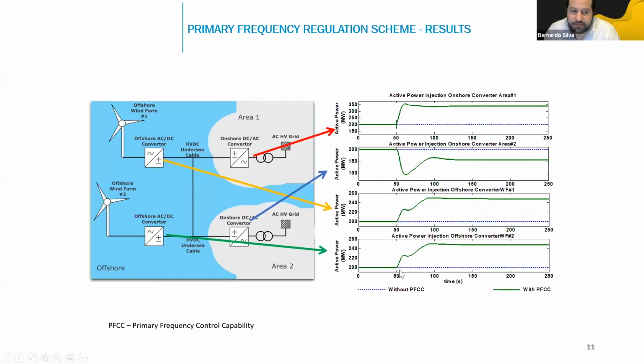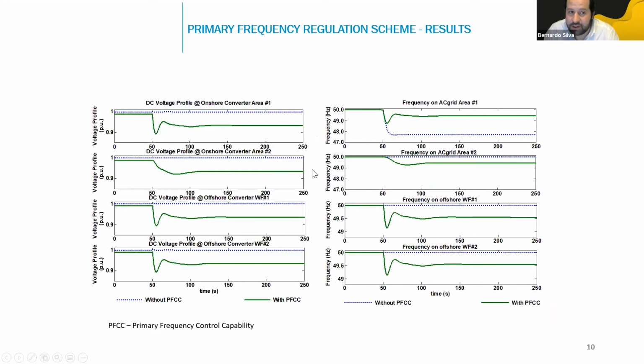Why is this happening? Because the control is operating well. This control, looking at the green lines, enables power injection towards the affected zone, achieved by two means. The unaffected converter, the onshore one, area 2, also helps mitigate frequency excursions, which is why we see a small frequency disturbance on area 2. We are sharing the problem between the two areas.